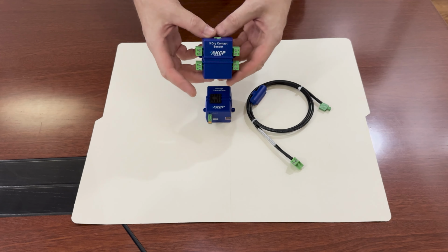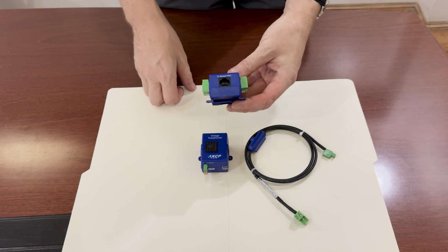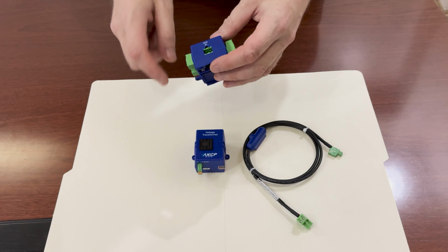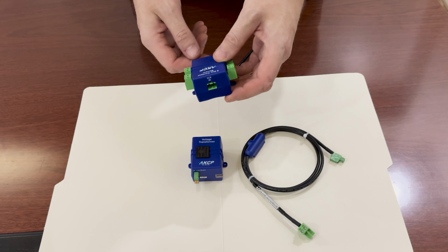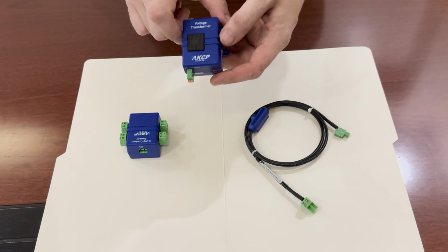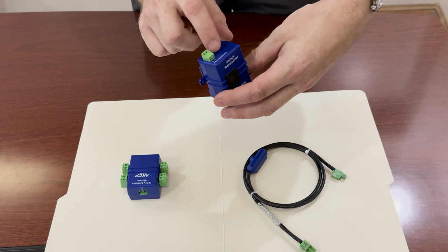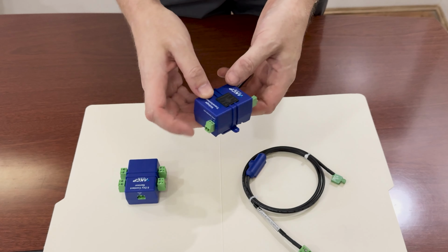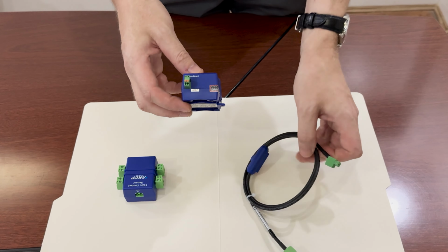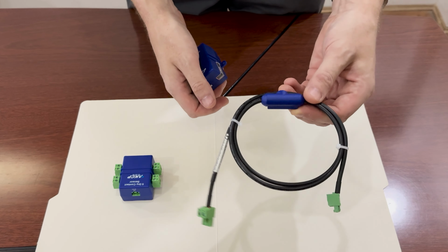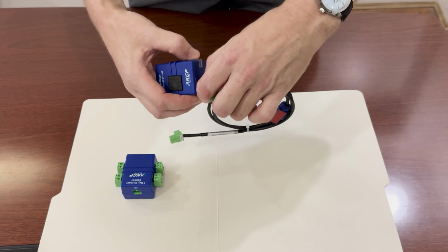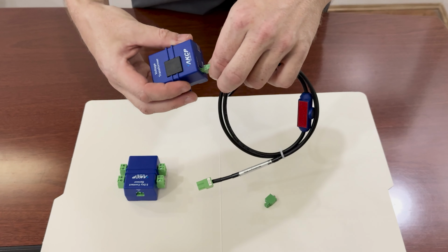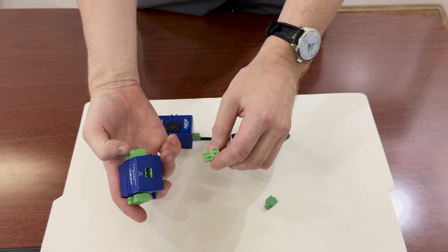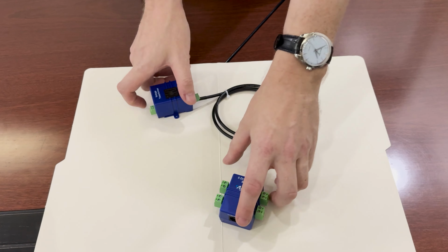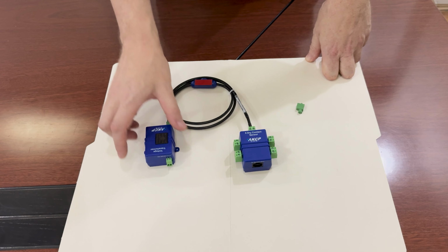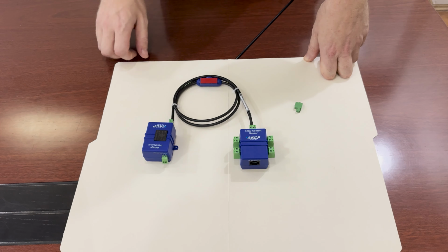So here we have our 5 dry contact sensor, or the 5 DCS. This goes back to a sensor port on the SP Plus, and then we have our 5 dry contact inputs on here. Now, this is our voltage transformer. You would connect from 100 to 300 VAC on the input side here, and on the output side, we connect this to the opto coupling board, which is the little board that's on this opto isolation cable. So you would plug this into the output side, and then the other end goes into the dry contact input on the 5 dry contact sensor. So now we've got an AC voltage detection fully isolated from our 5 dry contact input.